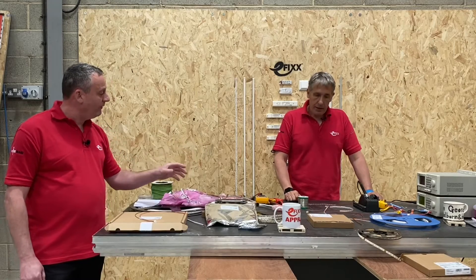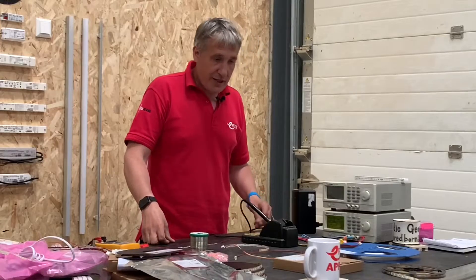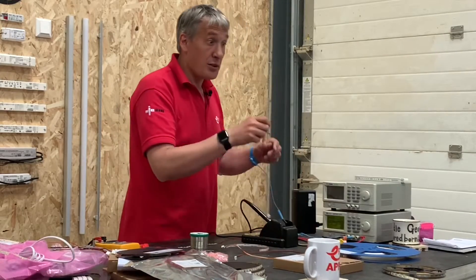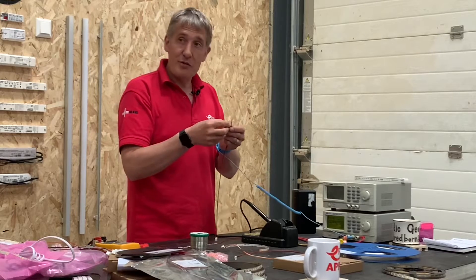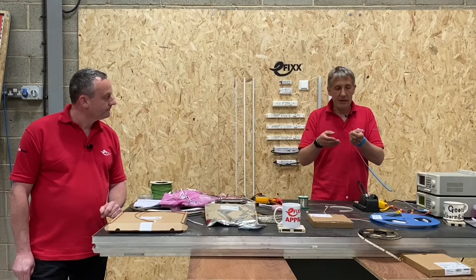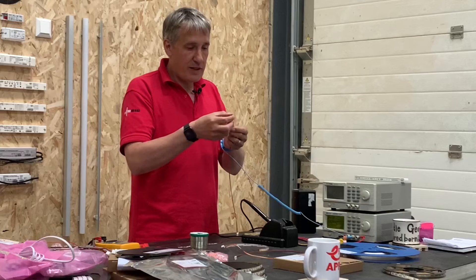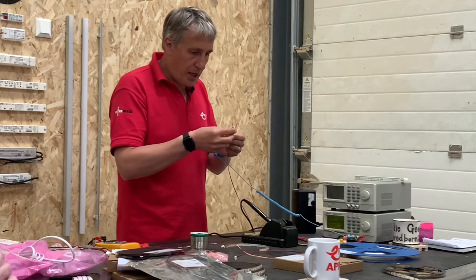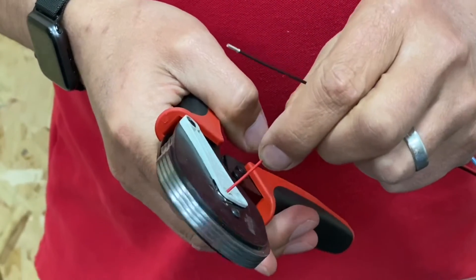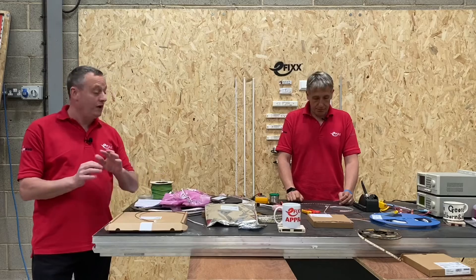So we've done that by tinning the ends and tinning the LED strip itself. Is there a tip or trick to make that process slightly easier? Across EFIXX we love a ferrule. Instead of tinning conductors, you can use ferrules — tinned copper sleeves — to miss out one of the tinning processes. If you've got a lot of LED tape to do, prepare these in advance. They create a neat, almost standardised connection across lots of LED tape.